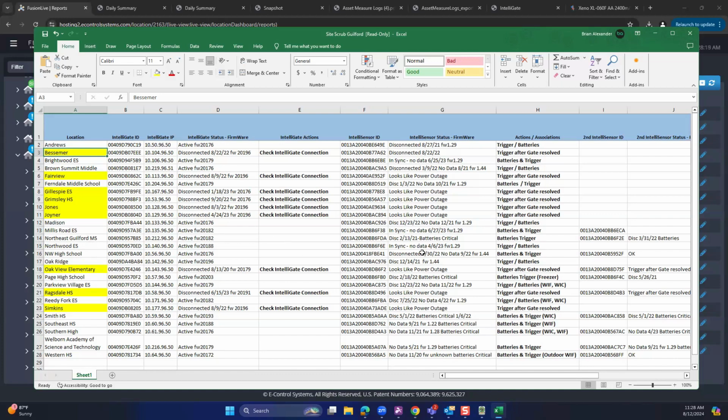The rest of these sites, a lot of them have been down, some more than a year, some more than 2 years, just due to batteries. Whether the batteries were changed and the person didn't trigger the unit, or they put the wrong batteries in, or put them in wrong, I'm not sure. But what we show as the last time they were online, they had the critical battery. So usually we just change the batteries and re-trigger the unit. Sometimes, if it's been really long, we'll walk somebody on site through a short-out procedure, and then re-trigger them and reconnect these things.